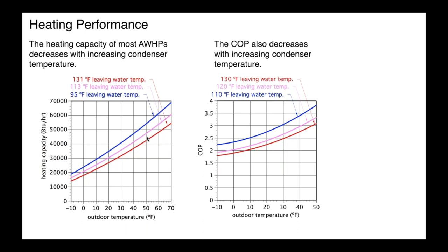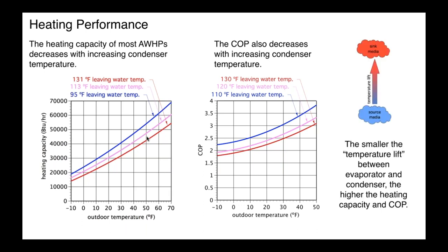So as designers, we're trying to optimize the coefficient of performance in the system, because ultimately that'll affect the number of kilowatt hours of electricity that a given heat pump in a given building is going to require. And I'd like to explain this again. I'm sure many folks watching today are familiar with this concept, but when we look at a heat pump as just a very generic idea, we have a source media, a low temperature media, could be water, could be air, that we're extracting low temperature heat from, and we're pumping that heat to a high temperature media. And the thermodynamics guys would call the low temperature media the source of the heat. And then the word sink means where we're dissipating the heat.